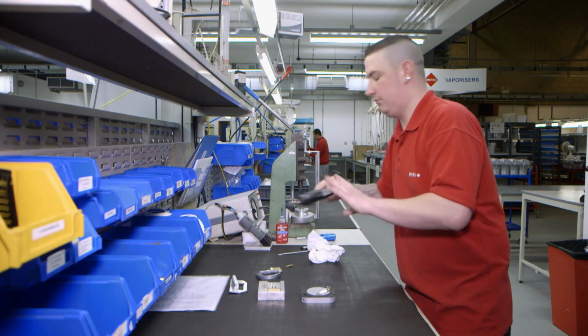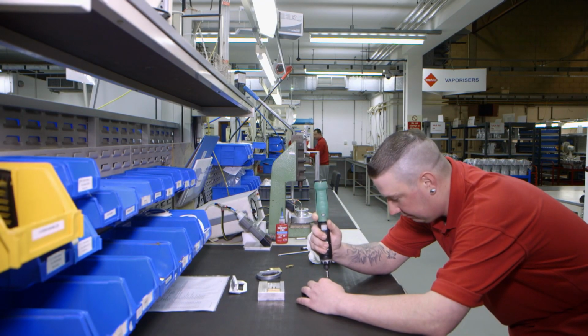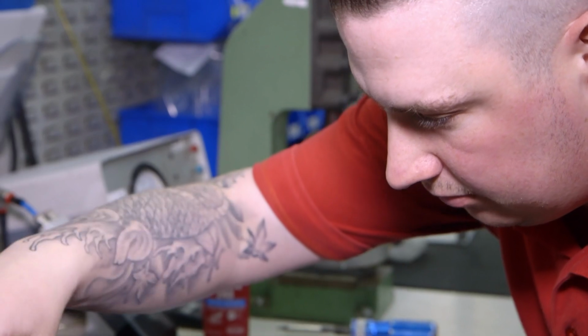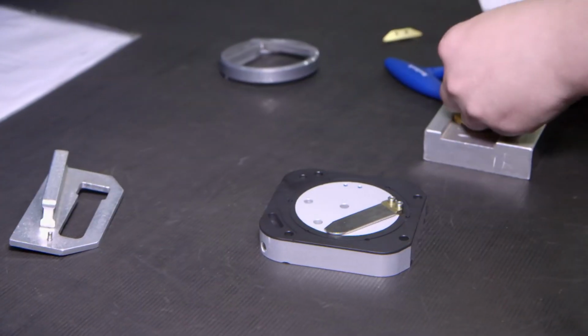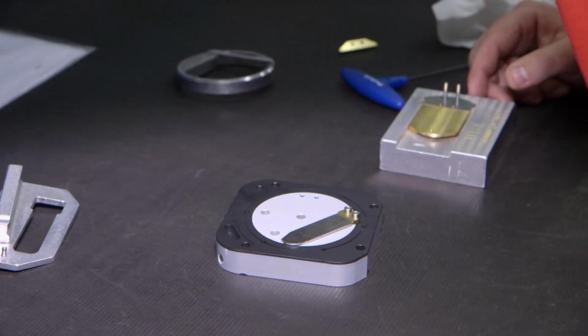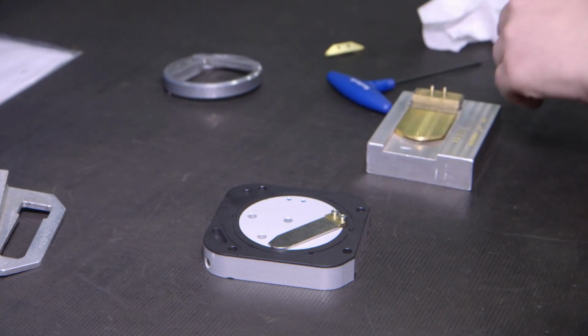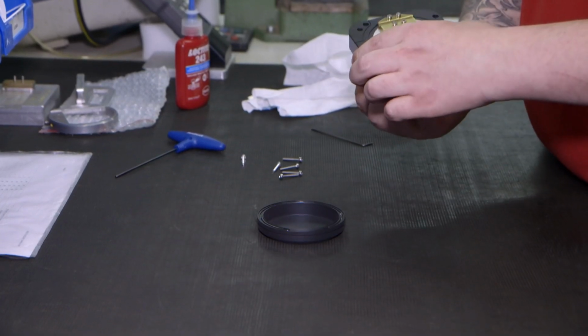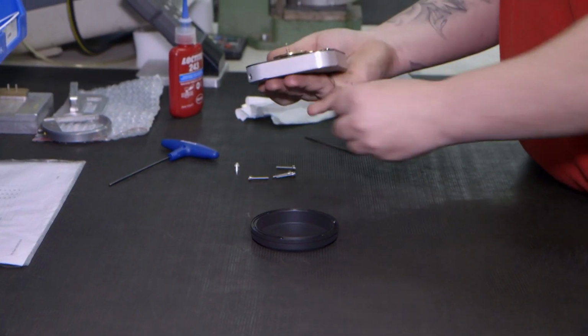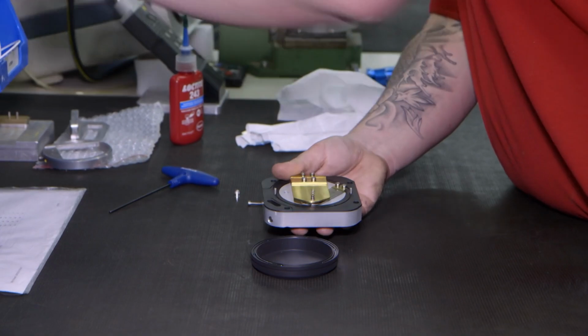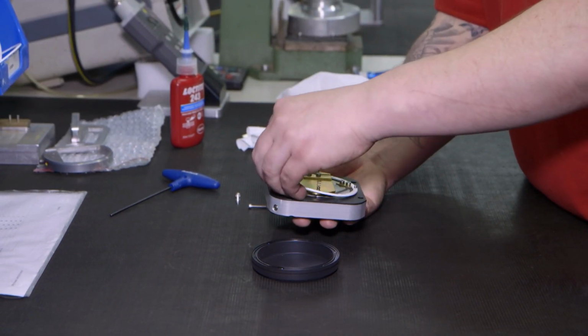Another line builds the vaporizers, which are one of the key parts of the anesthetic machine. They convert the liquid anesthetic to a gas state and add controlled amounts of the gas anesthetic to the oxygen that is flowing through the machine. Because gases' properties vary at different temperatures, it is important that the temperature is constant, so compensators are fitted to regulate the temperature of the gases.